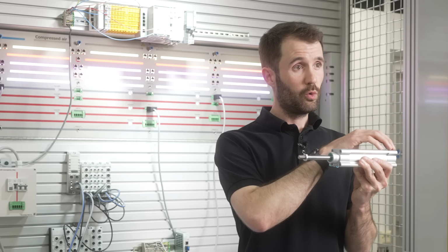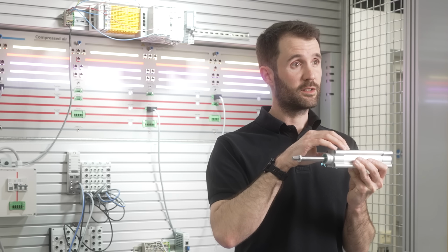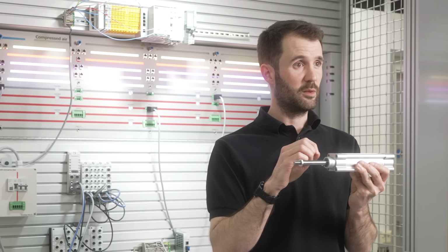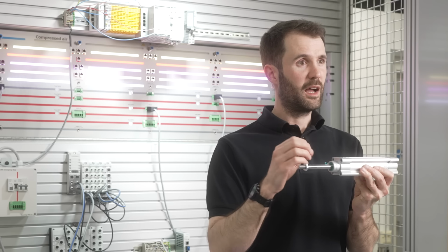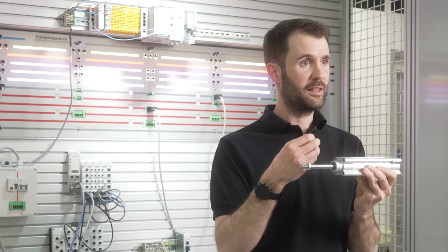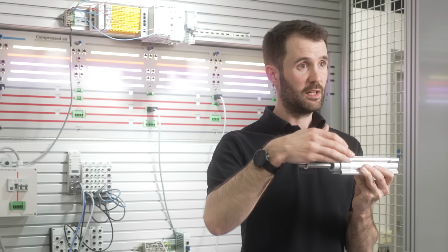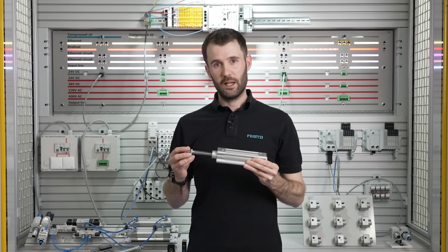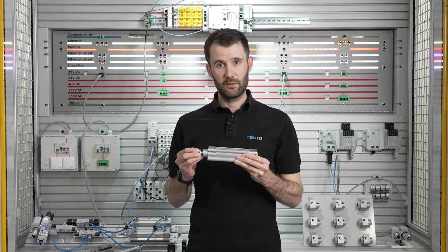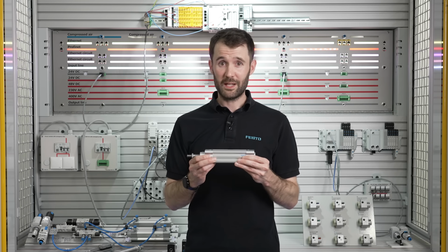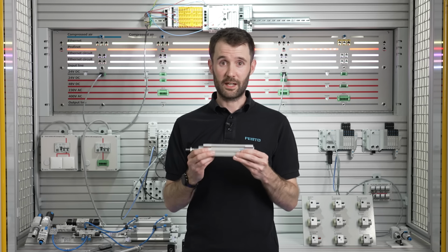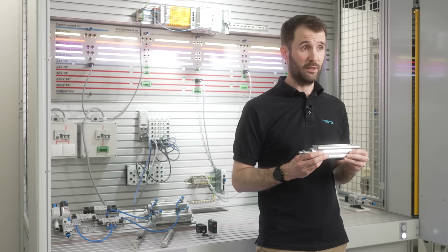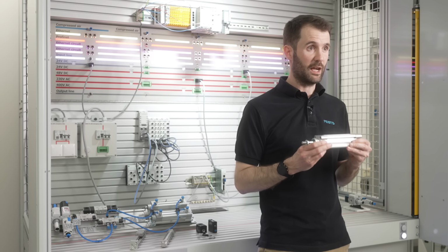And finally, all of the pneumatic cylinders typically have grease inside of them to allow a smooth operation. But let's say if lubricants came into the system, this could wash all that grease away and cause what we call dry running. And in this case, all the seals inside the cylinder would start to fail and wouldn't perform as we would like. Now, with preventative maintenance, we can detect all of these. But preventative maintenance is only as good as the technician who's performing it. Preventative maintenance does not remove reactive maintenance, it just minimises reactive maintenance.